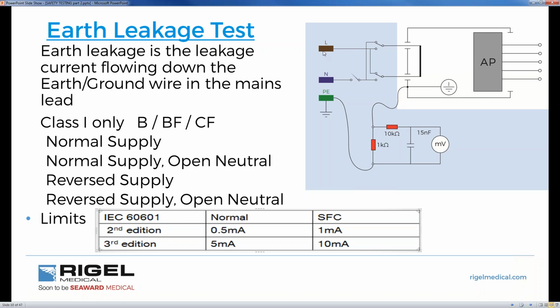So that power consumption, let's say the total system is 100 milliamps. Well, let's say we have 99 milliamps flowing between live and neutral to power the device to make sure that it operates. It can do its diagnostic work or whatever the medical device requires. Well, if the system is 100 milliamps and the functional current is 99, then 1 milliamp must go missing in the system. That 1 milliamp that goes missing in the system is what we call non-functional current, or leakage current. So how does this happen?